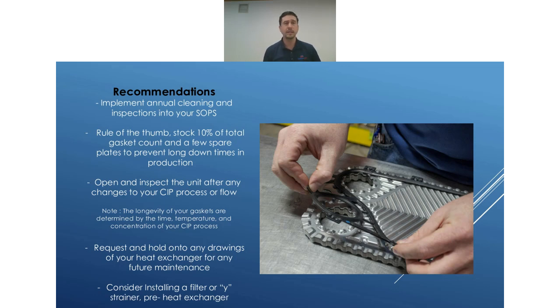What comes with your heat exchanger also is a set of drawings, and those drawings basically go over everything about that heat exchanger - what type of gasket you have, plate orientation, gasket types, anything and everything you need to know, closing dimensions. You want to make sure you're holding on to those. Put them in a safe place, because there may come a time you have to open that unit up in a surprise moment, and you want to make sure you have those on hand. That really does seem like a no-duh thought, but it's important those are held onto as well.